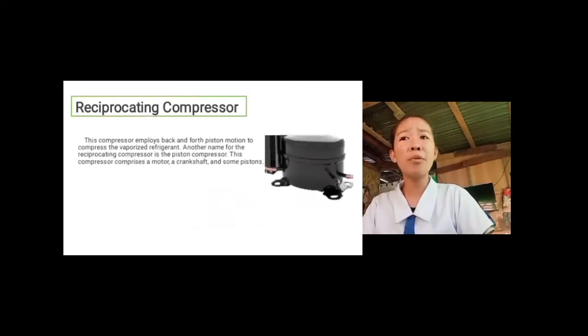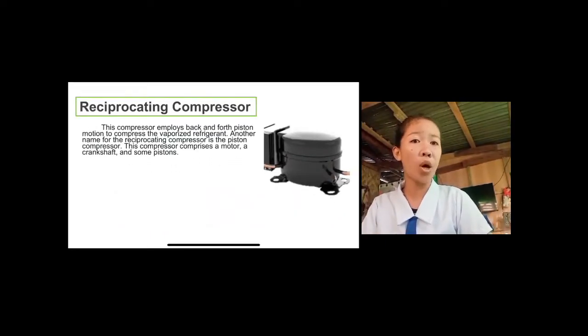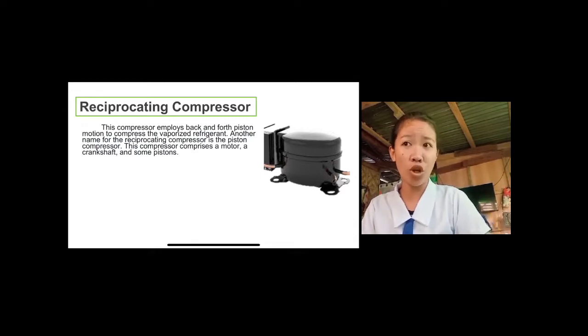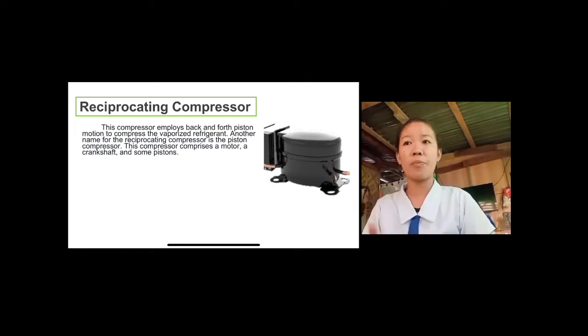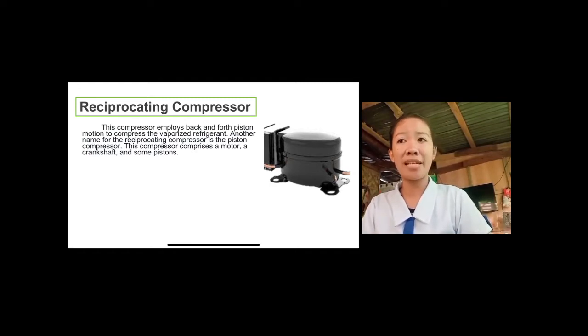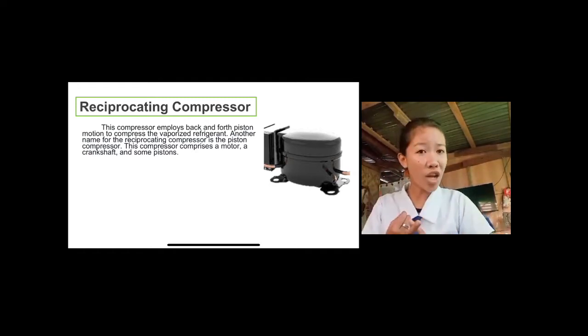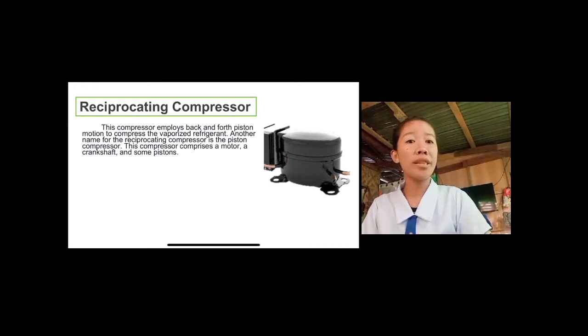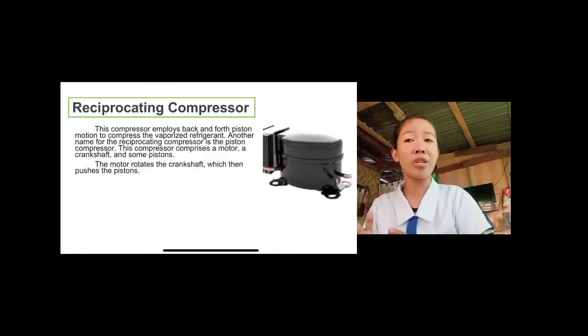A reciprocating compressor is a compressor that employs back and forth piston motion to compress the vaporized refrigerant. So what is the function? It employs back and forth piston motion. Another name for the reciprocating compressor is the piston compressor. This compressor comprises a motor, crankshaft, and some pistons. The motor rotates the crankshaft, which then pushes the pistons.